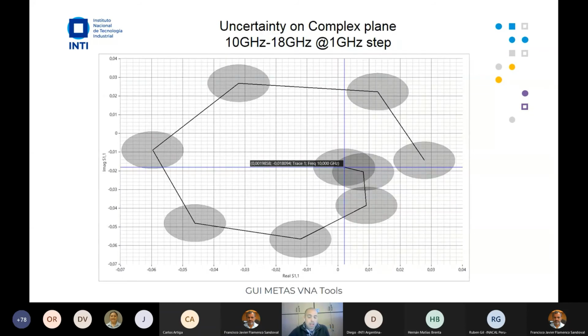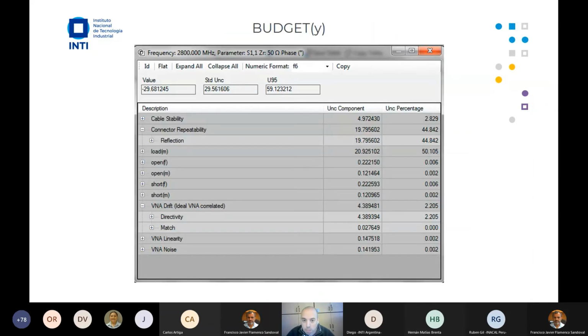The reality is that you don't have an uncertainty budget now, because we are not using a spreadsheet and Excel uncertainty evaluation. So if a reviewer asks you for your Excel budget, you're going to say, I don't have it. But before the non-conformity, you just type the budget command and it's going to pop up. And you see the budget is generated automatically, by walking through this tree concept.